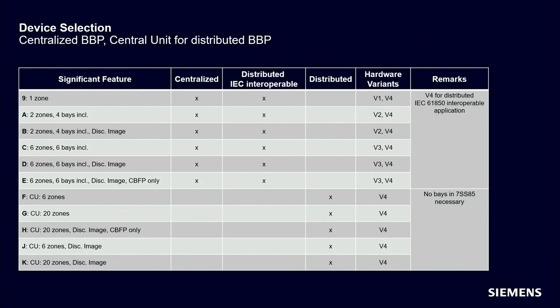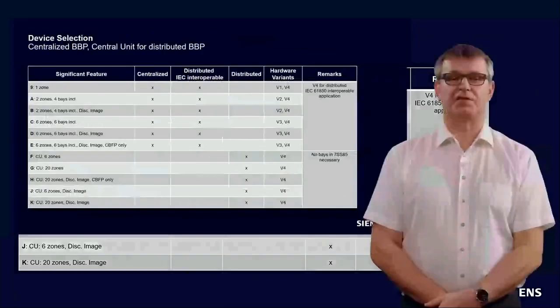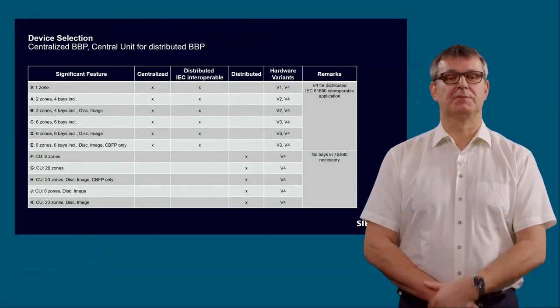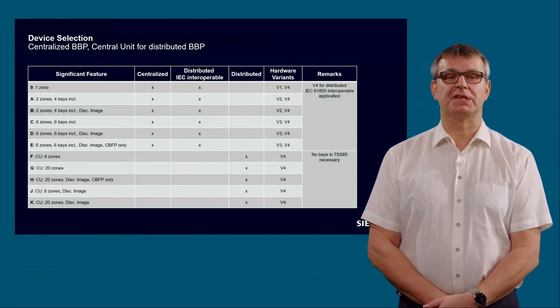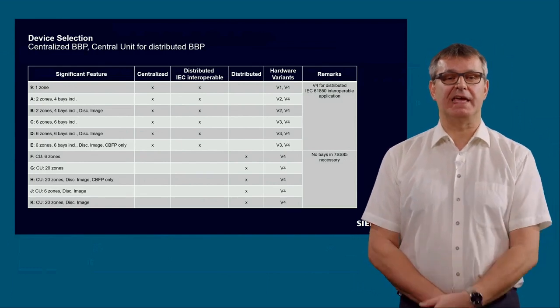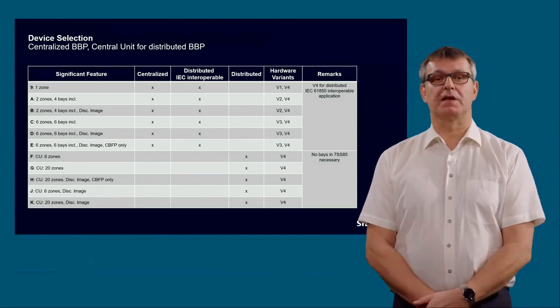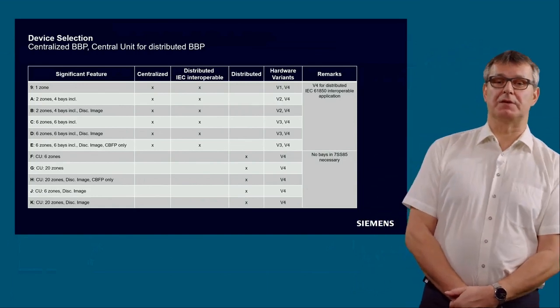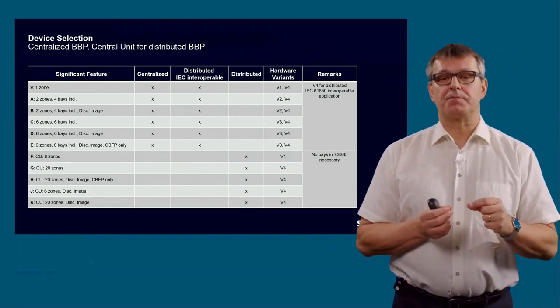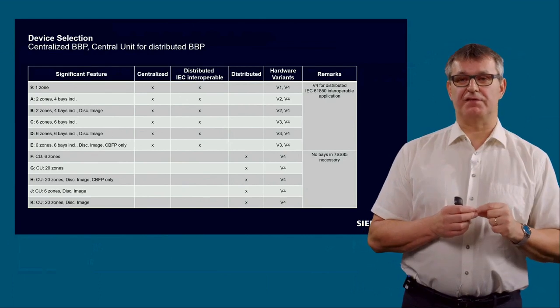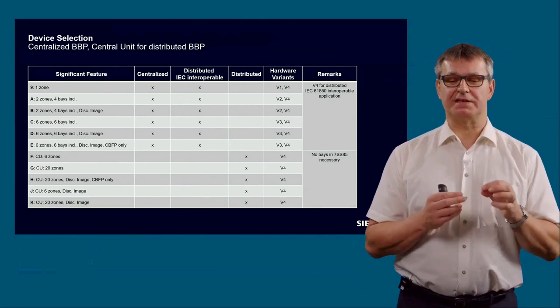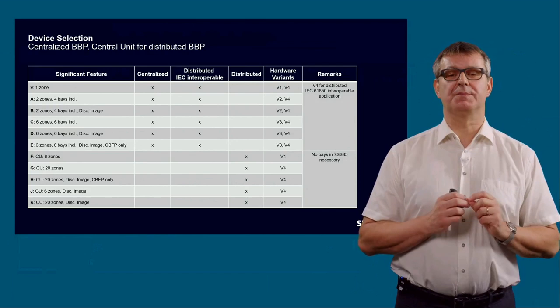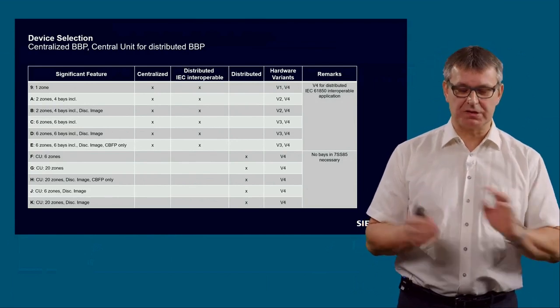And you have the significant feature for the 7SS85CU with a disconnector image, the J with 6 zones, and the K, the biggest one, with 20 zones and disconnector image. And very important, with the 7SS85CU solution, it is always a distributed approach. There is no way to use it as a centralized bus bar protection. There are no bays necessary and therefore also no bays included.